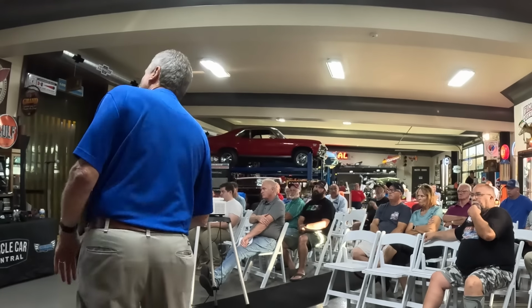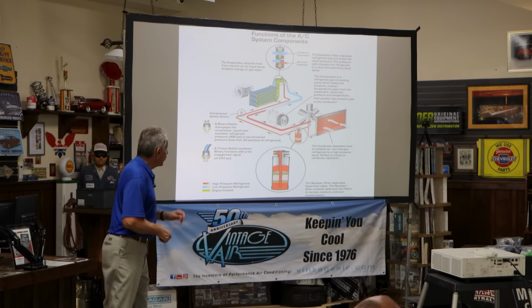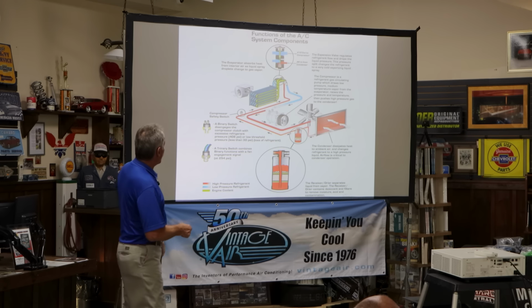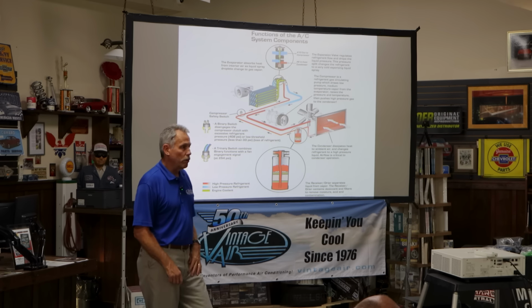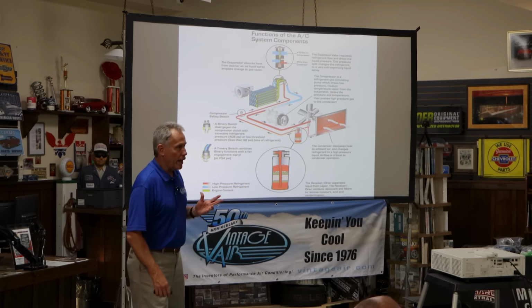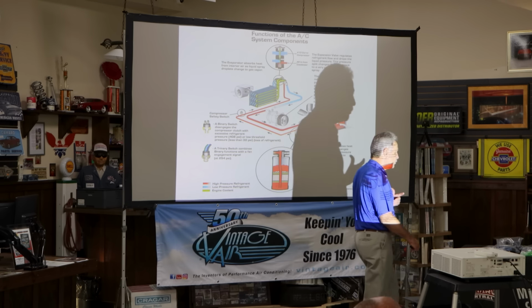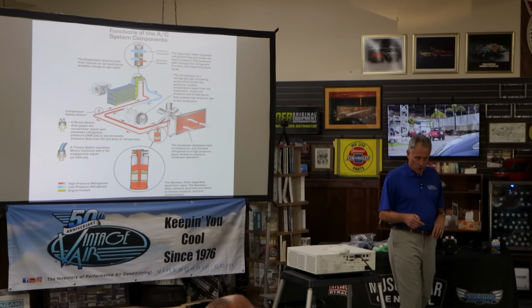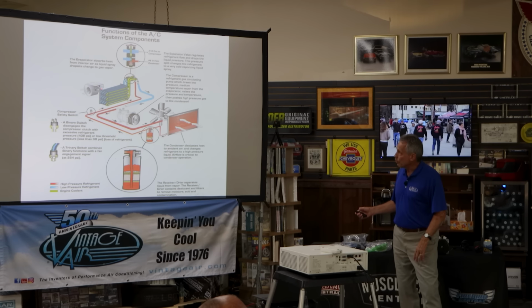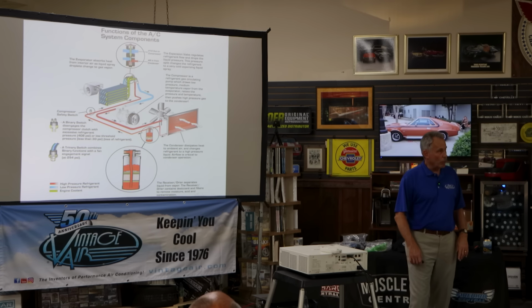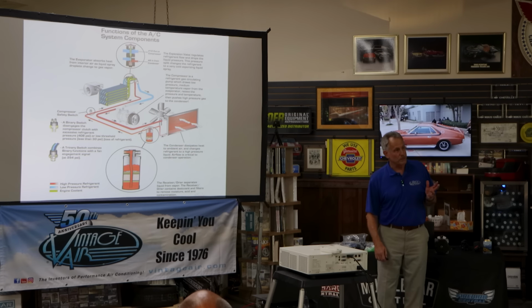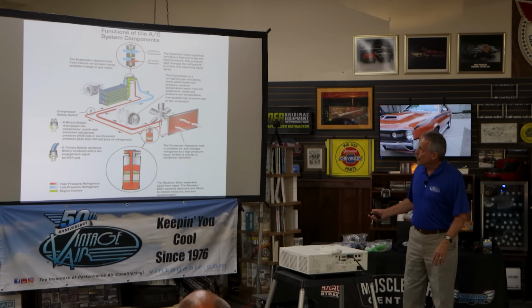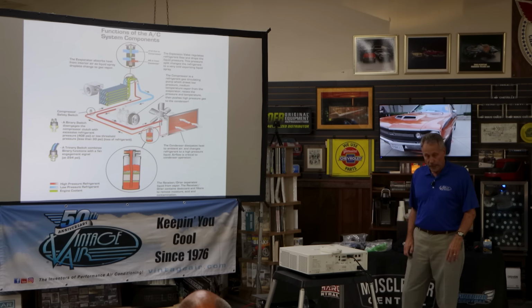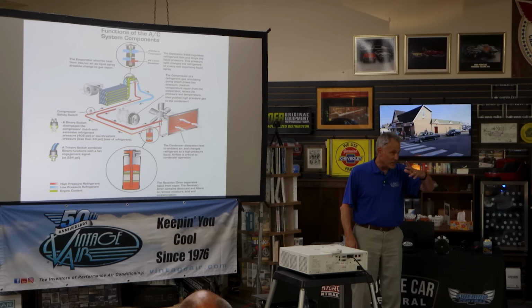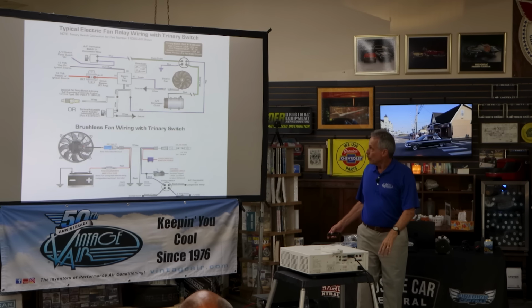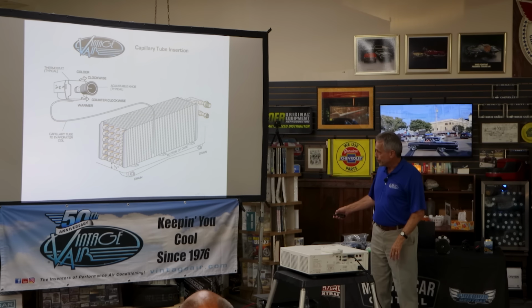We talked about the coil, how we pull in hot air, blow it across the coil, and remove that heat from the air. As we remove the heat from the air, it loses the capacity to hold moisture. So as that air comes across the coil and loses that capacity, the moisture forms on the coil fins and becomes droplets. Through gravity and the help of the blower, that moisture, the condensate, falls to the bottom of the case and then goes out through the drains at the bottom.